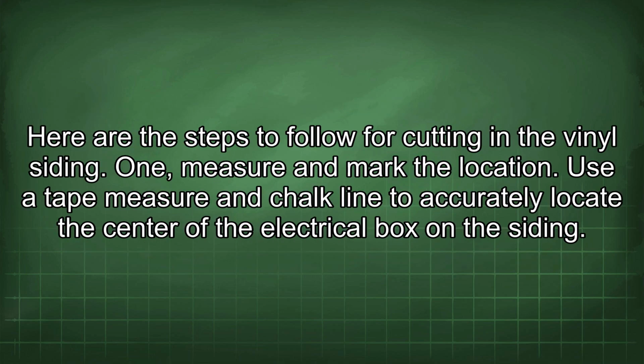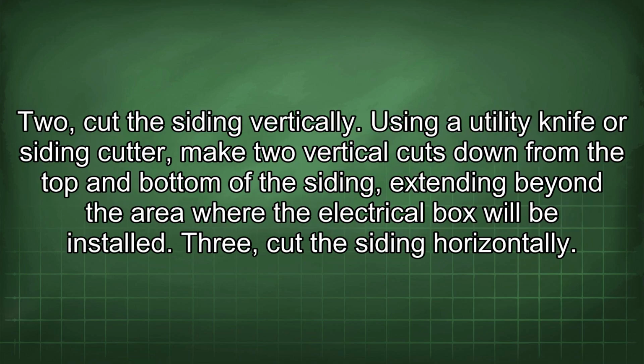Here are the steps to follow for cutting in the vinyl siding. 1. Measure and mark the location. Use a tape measure and chalk line to accurately locate the center of the electrical box on the siding. 2. Cut the siding vertically. Using a utility knife or siding cutter, make 2 vertical cuts down from the top and bottom of the siding, extending beyond the area where the electrical box will be installed.